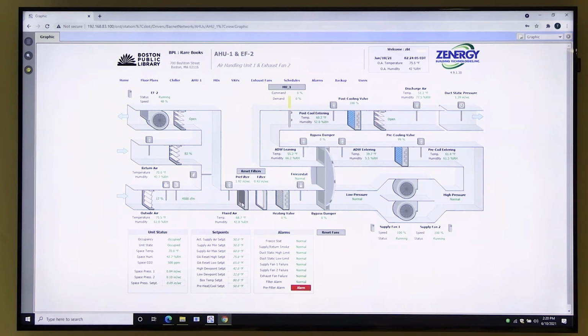This red background and that dirty thing is just an alarm that's triggered after the pressure being too high for an hour. So once you change the filters, you have to hit that button to clear that alarm. So we'll at least be clear for the next hour.